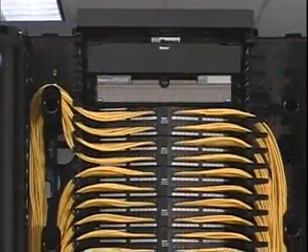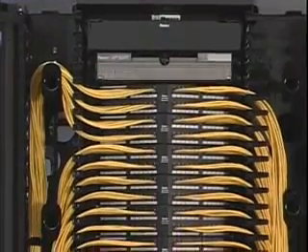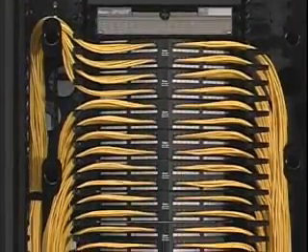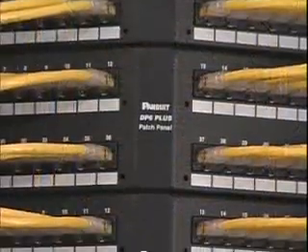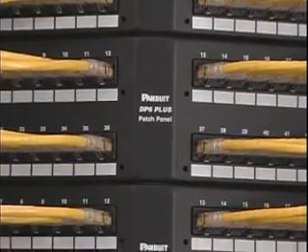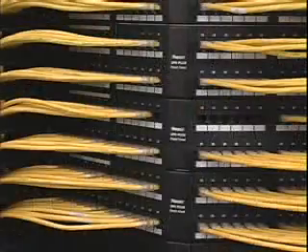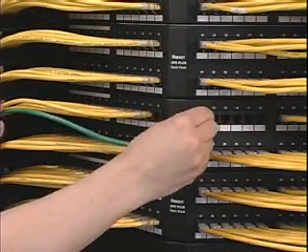This requires that the patch cables on the left side of the panel be routed to the left and the right side to the right. Do not route cables on the left side of the panel to the right and vice versa.